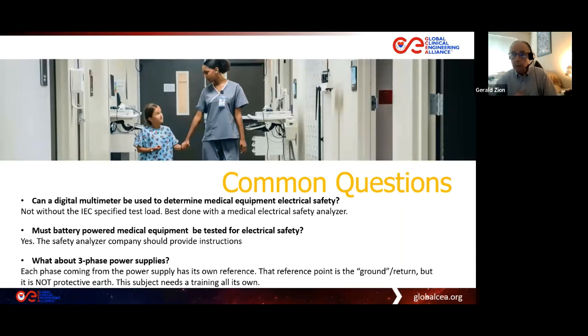All right, a couple more questions and we're almost finished here. Can a digital multimeter be used to determine medical equipment electrical safety? And the answer to that is not without the IEC specified test load. So you would have to improvise that test load if you're going to use a digital multimeter. And my advice, from my previous job working with Fluke Biomedical in metrology and medical equipment quality assurance, is don't do that.